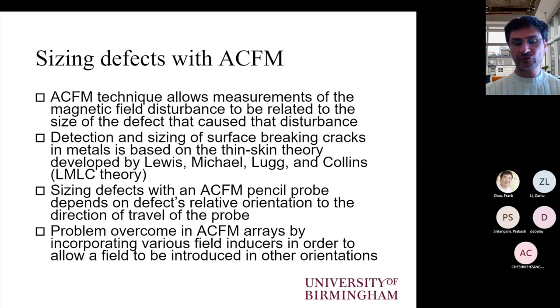But when we use the actual instrument, the software of the instrument does not recalculate the signals. Instead, it goes to a lookup table and it compares the signal we have obtained to what is already available in the lookup table as a calibration. So there are no further calculations incorporated in the actual industrial system. It is already loaded with the lookup table that the signals that we obtain in the field are compared with.